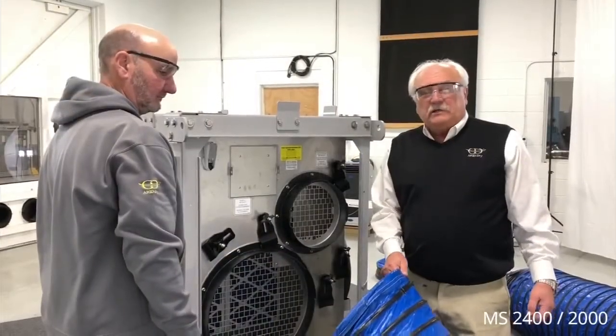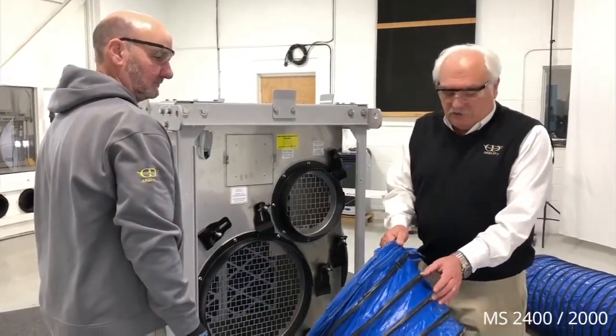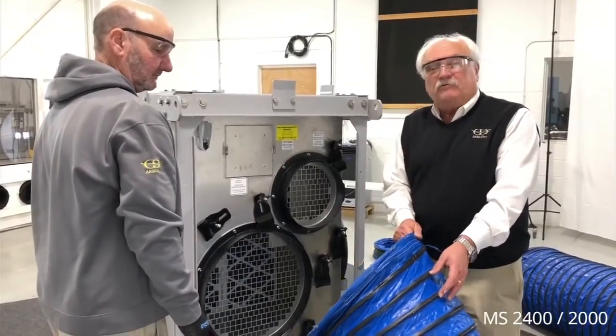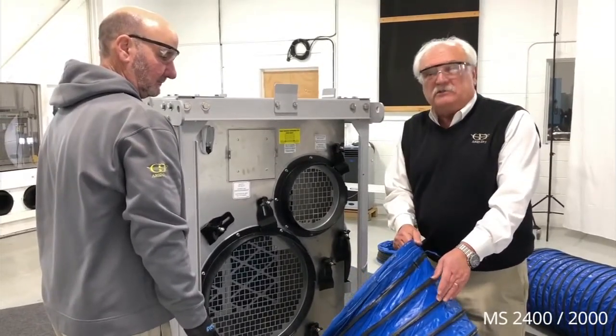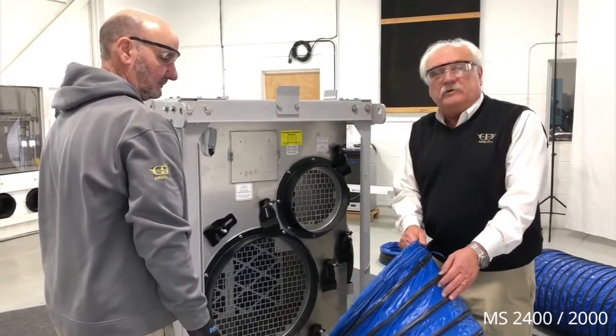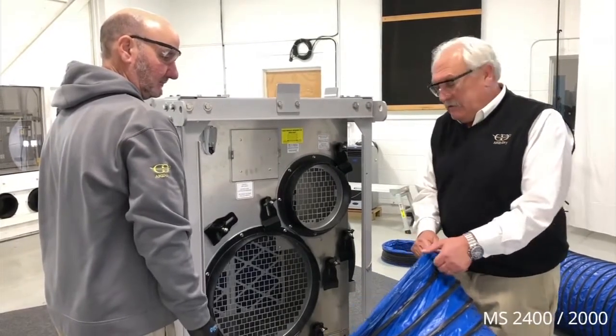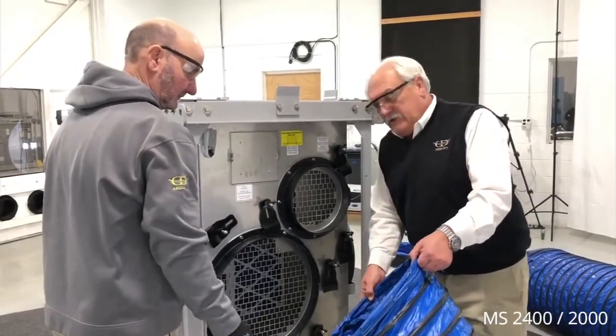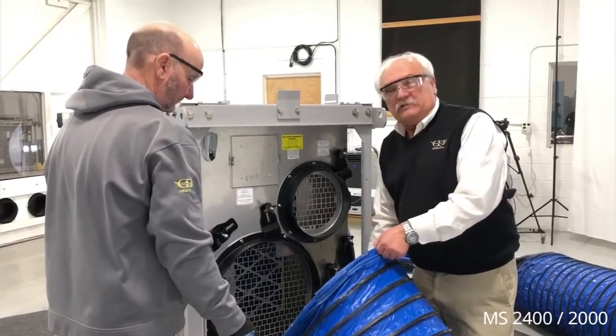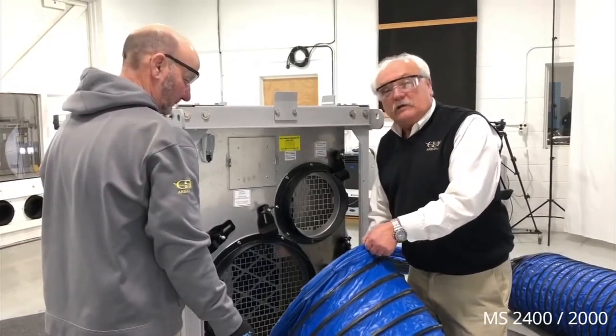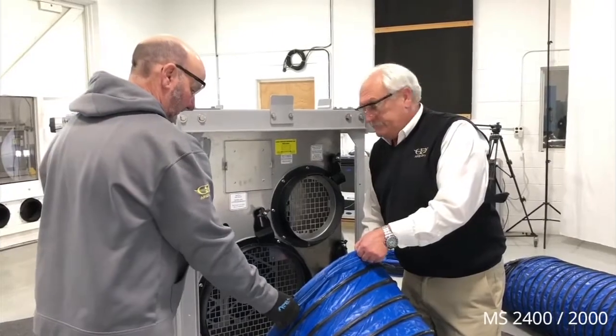The return ducting, we use 3-inch pitch ducting. So the dimension between the reinforcing ribs is 3-inch because this is a negative air pressure airstream and it can collapse the duct if it's not correct. We then take the duct and connect it to the 20-inch outlet on the unit using the quick connect duct clamps.